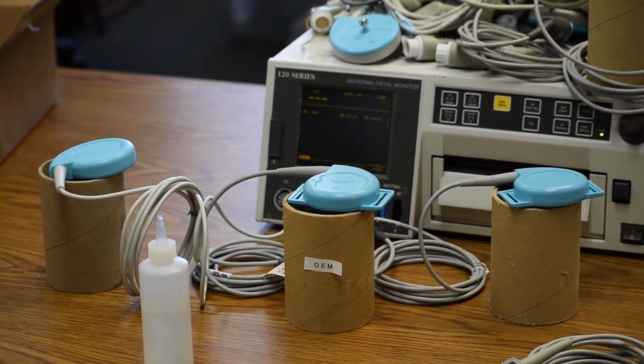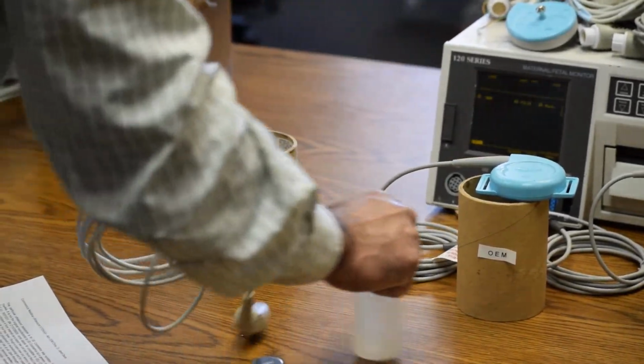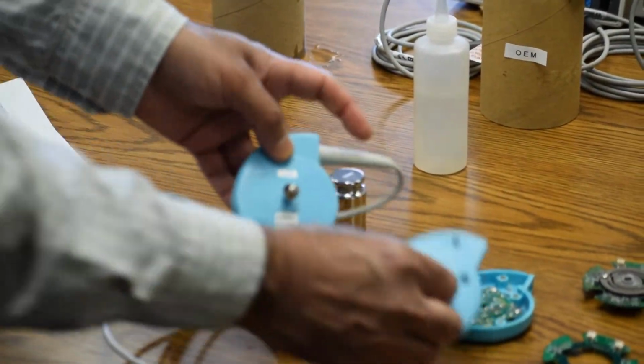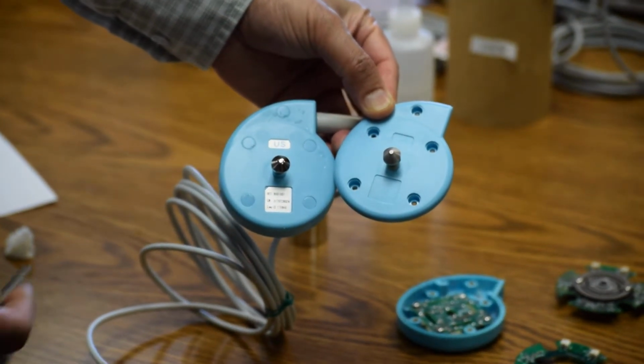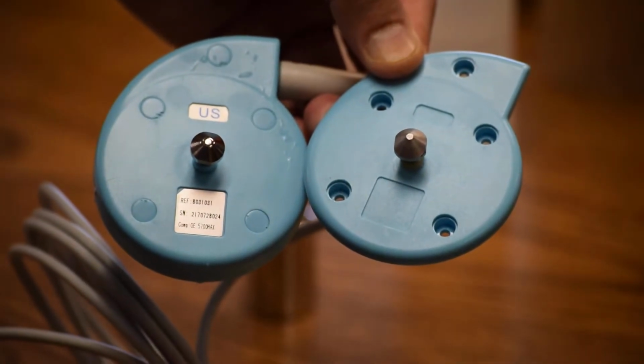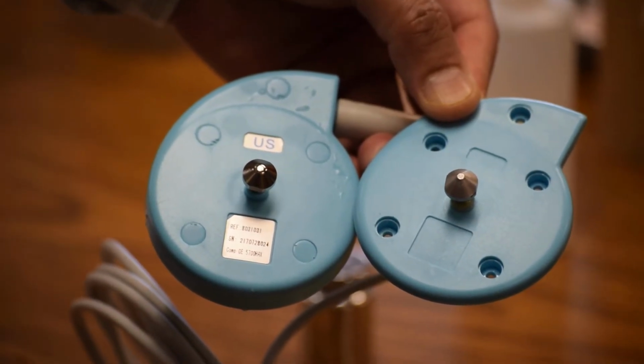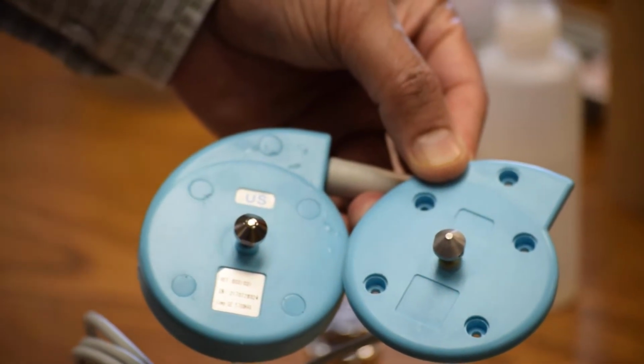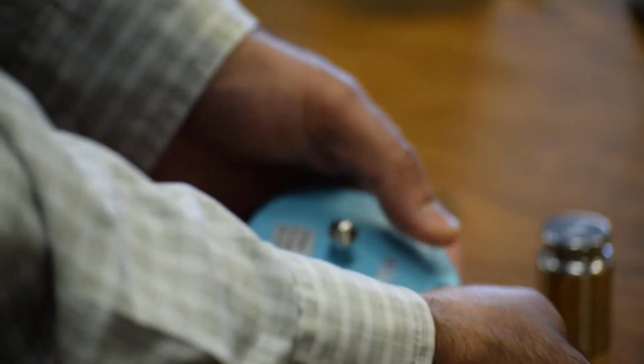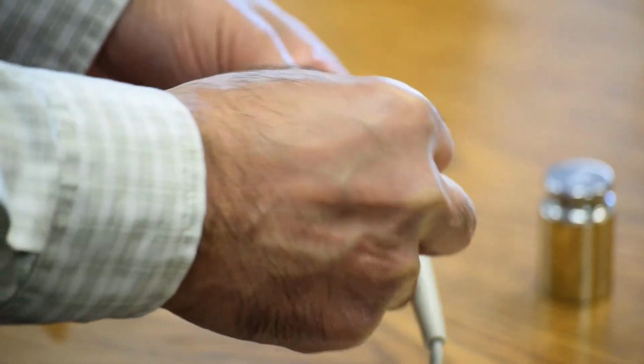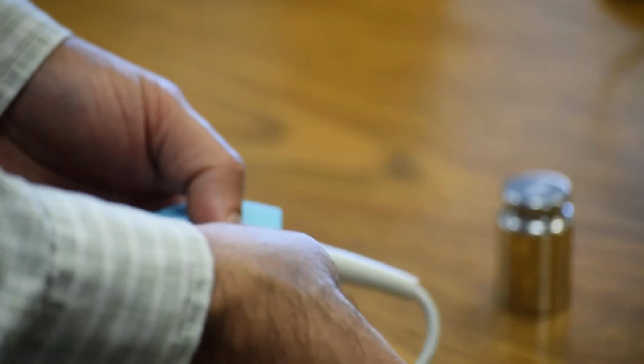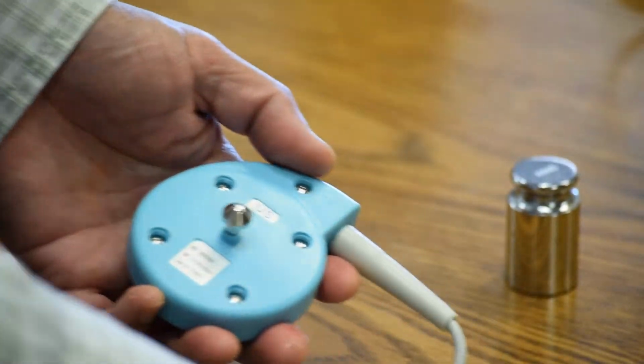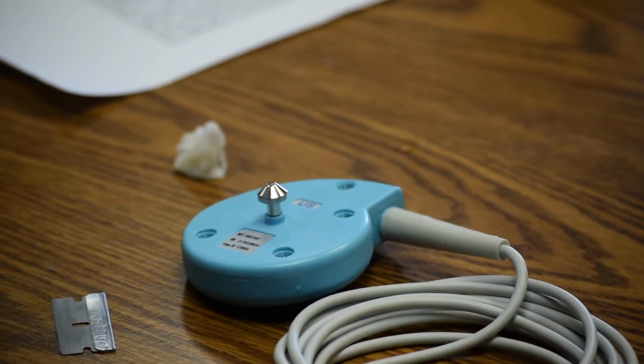Let's open this transducer and see what's inside. As you see, these are generic top cases. Anybody can make a label and put it there, which is not a professional process or in compliance with medical device regulations. The screws used are also poor quality. There is no water tightness. In place of Phillips plus head, slotted head screw is used. Most of the time we find aluminum screws, they get rusted and difficult to remove. The rust particles fall inside and aggravate the problem of spurious signal.